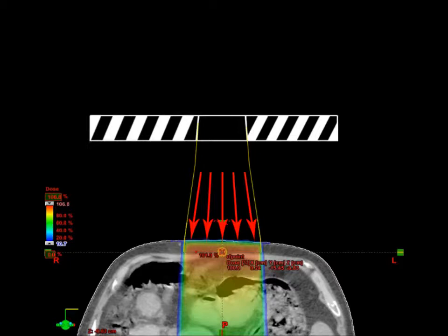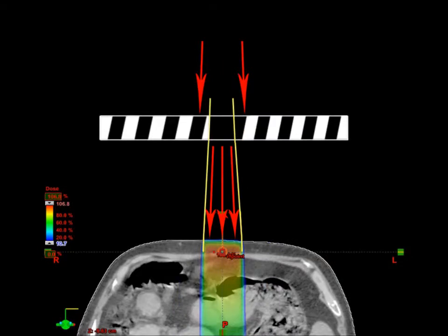Now if we shrink the field size, we can see that not all the scatter from the 10x10 is going through. This is represented by the red arrows hitting the collimation jaws at the top.